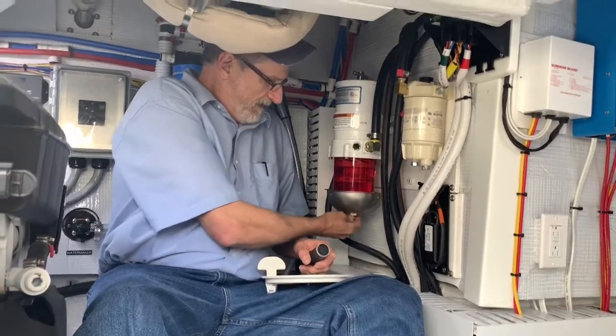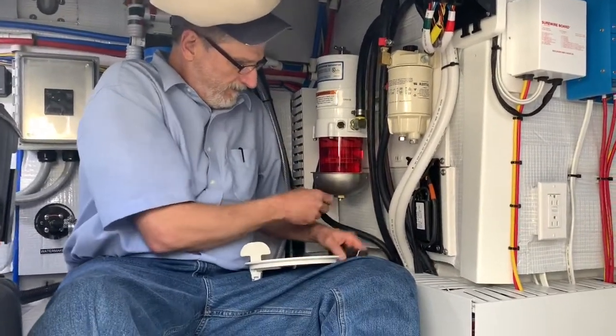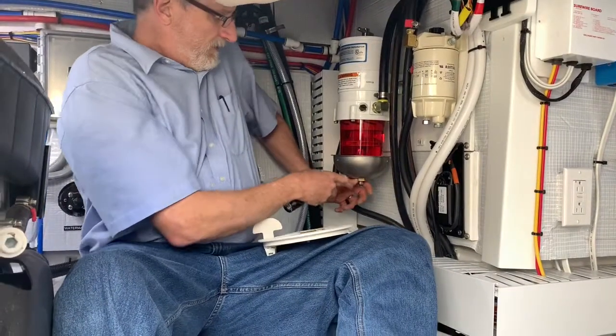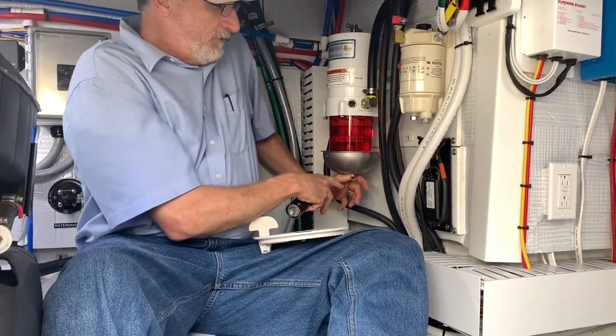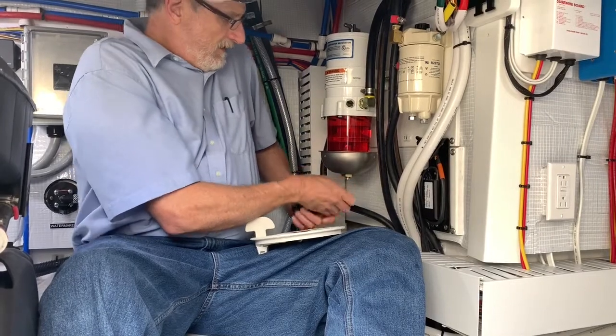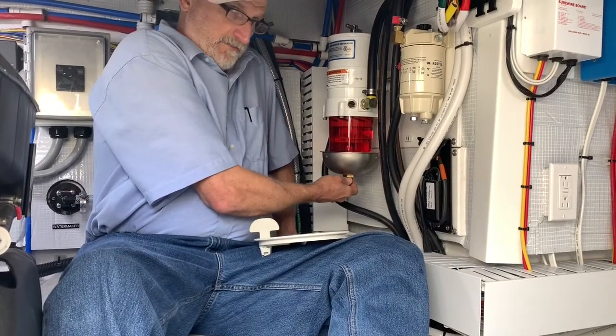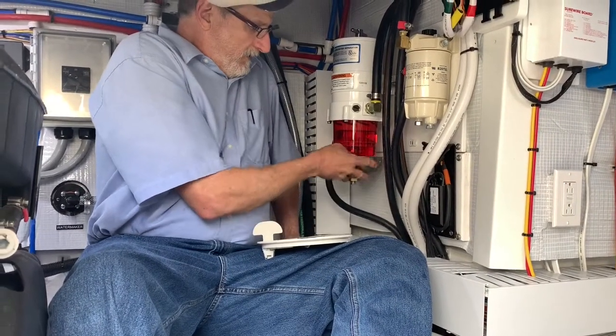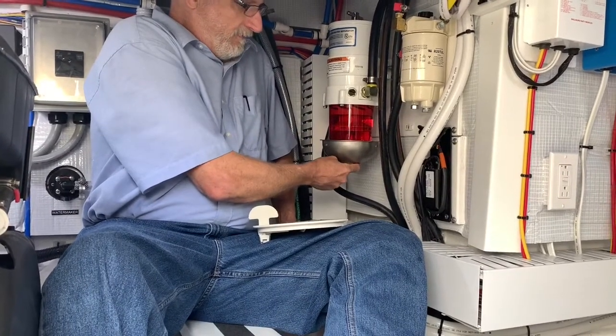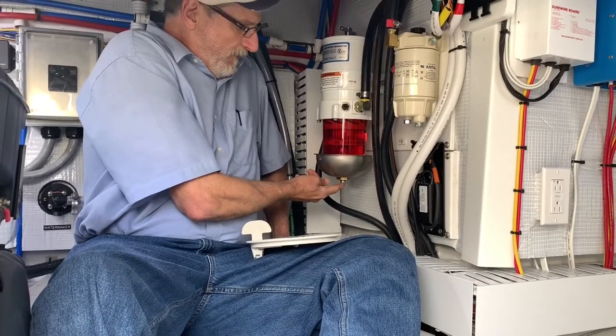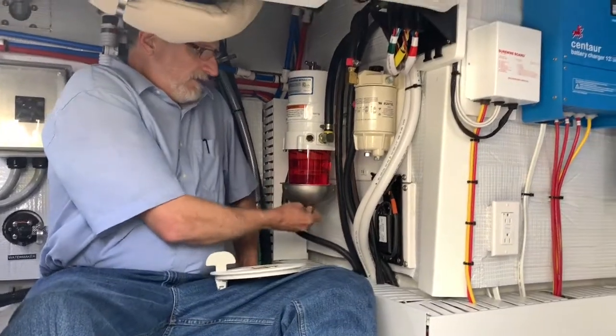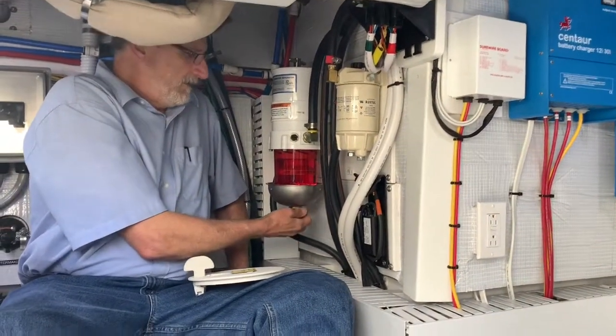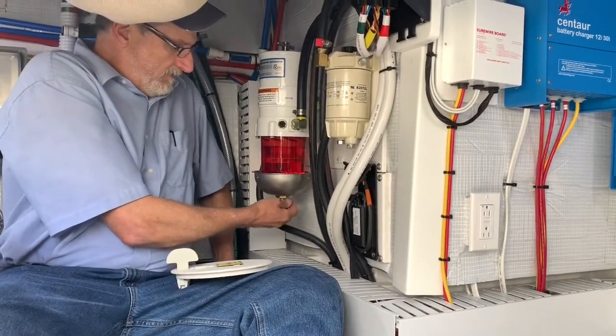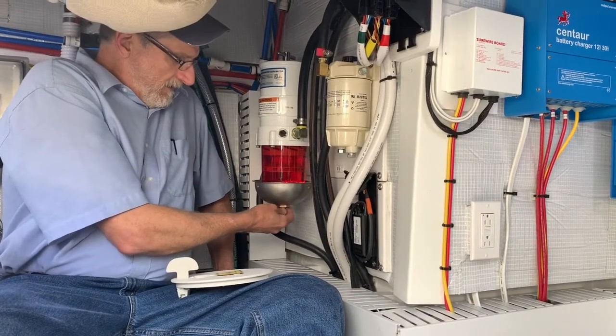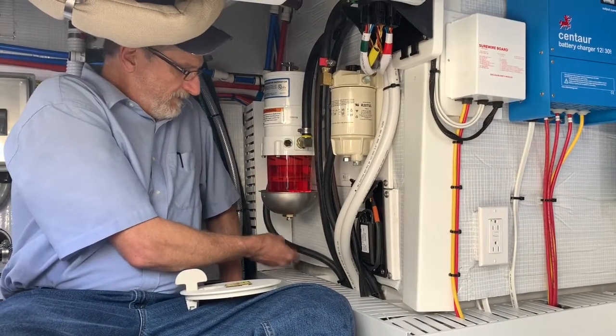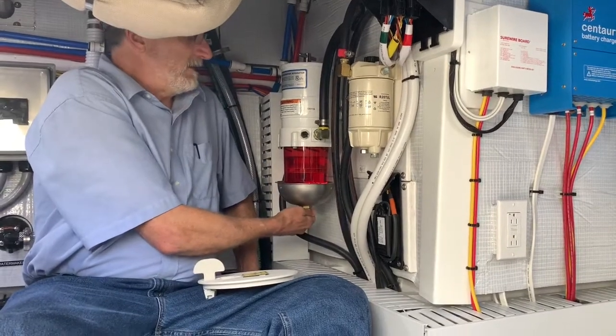You can drain that with this plug here. You'll need to hold the larger plug still with a large wrench and remove the smaller plug. The larger plug holds the whole assembly together, so that needs to not move—just the small inner plug. You can pull the plug out and drain the water out until you see diesel coming out, then put the plug back in.